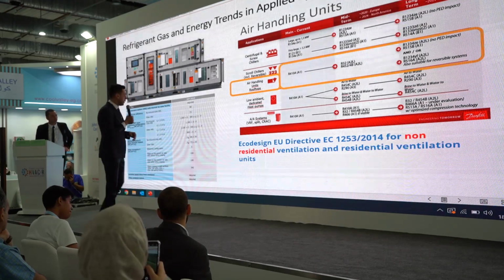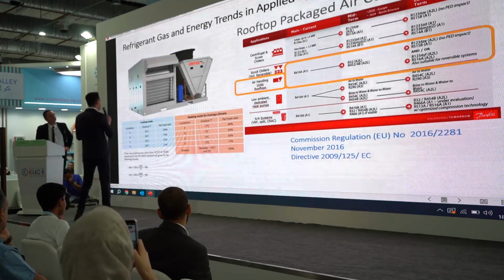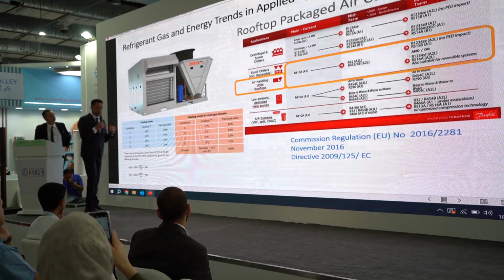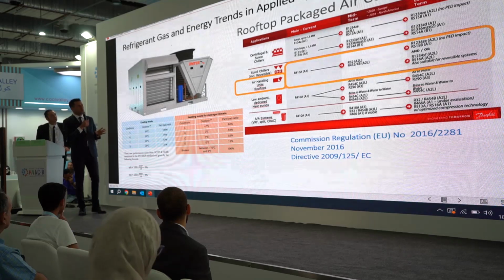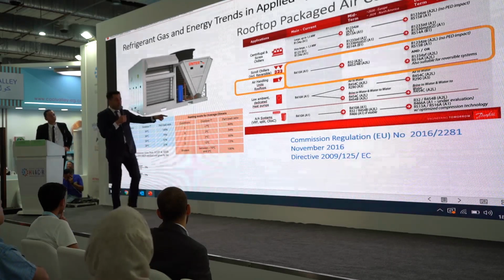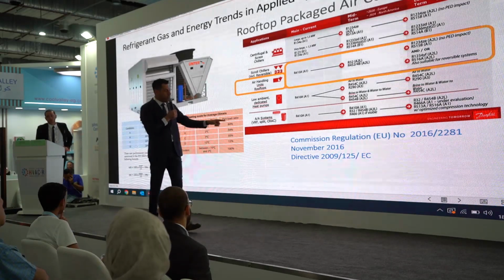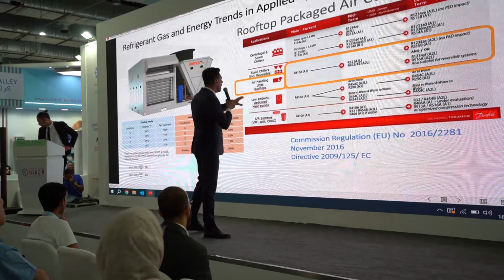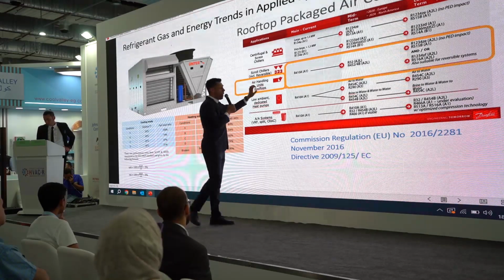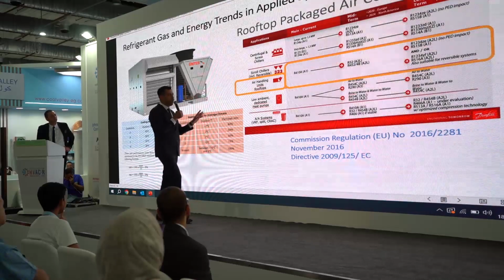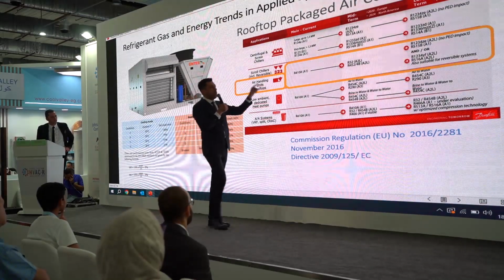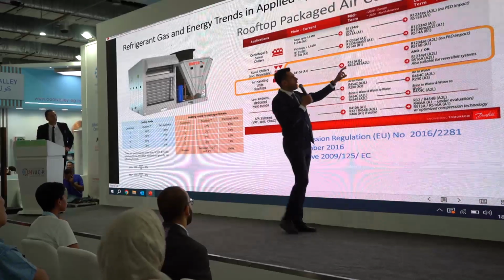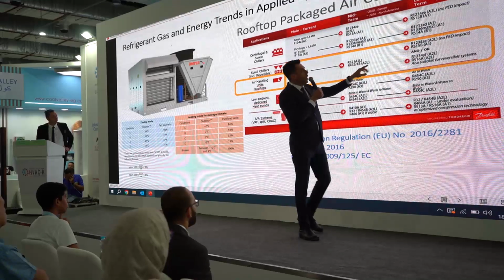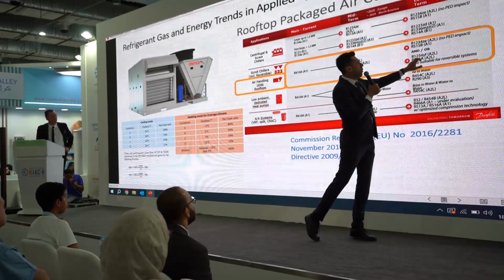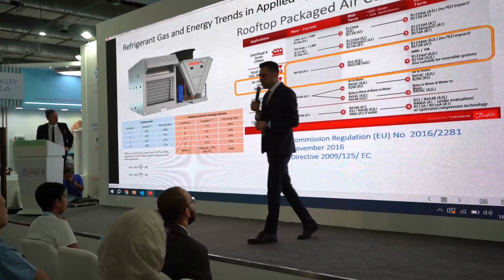These are facts. If we go to rooftop packages, that's a different story. Rooftop units, refrigerant-wise, with the Commission's designation and regulation system, gas-wise it's going to be similar to air handling units. Rooftops and air handling units today are 410, but tomorrow it's going to be replaced by 32, 454B, and in the long term replaced by other refrigerants.